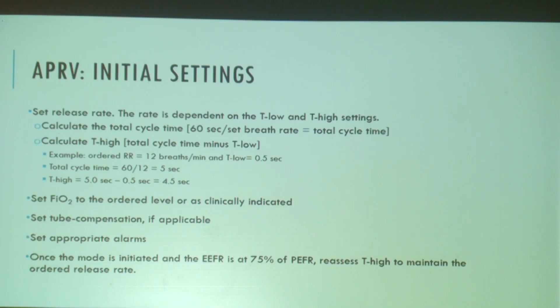I'm sorry, but how do you tube compensate in APRV? For the resistance, we just set the tube compensation on there, choose the size of the endotracheal tube, and there's a feature on the ventilator, and it will increase that pressure. The ventilator will realize what that resistance is and increase the pressure briefly when they have that spontaneous inhalation, beyond what we have the pressure set at. It'll ask for the size of the tube.